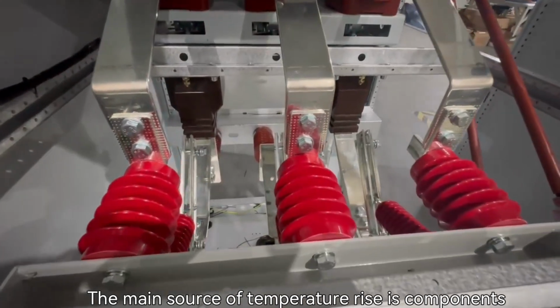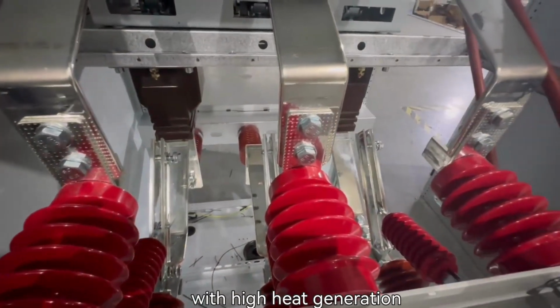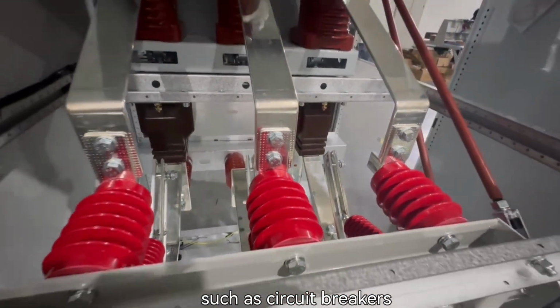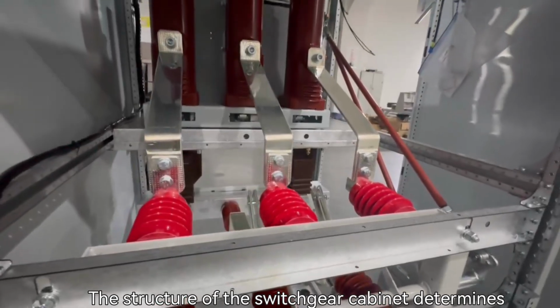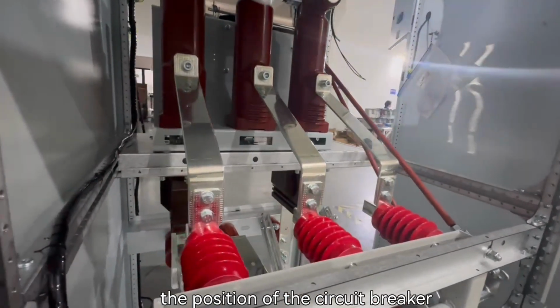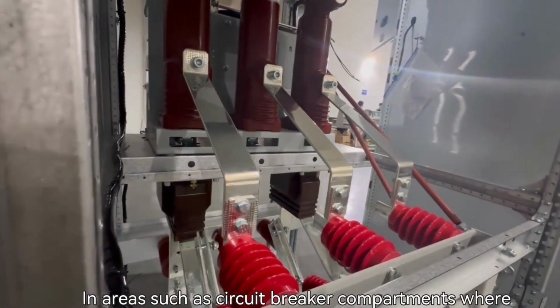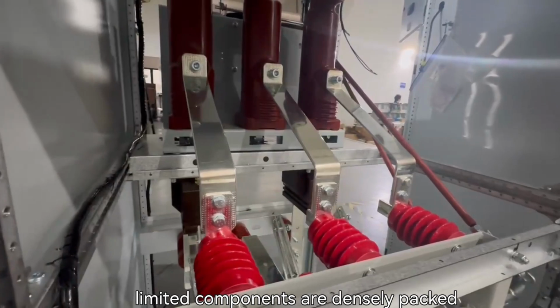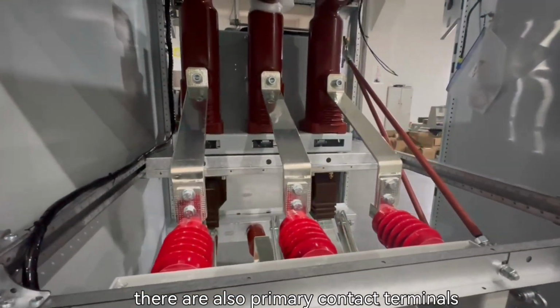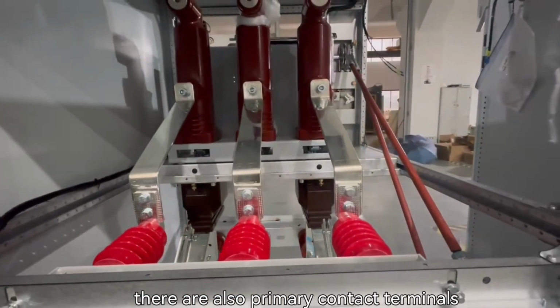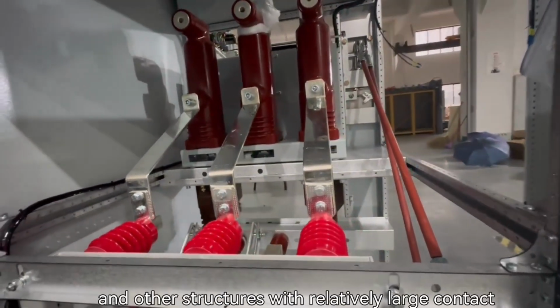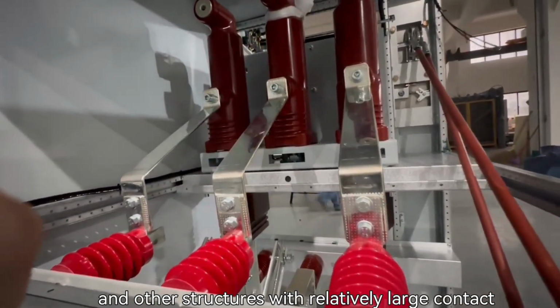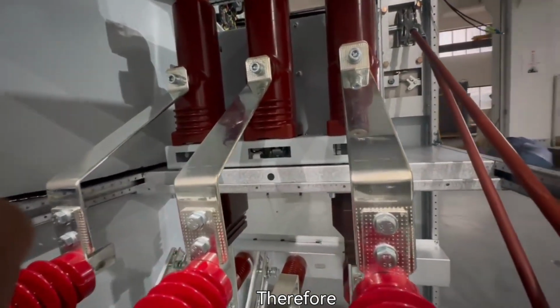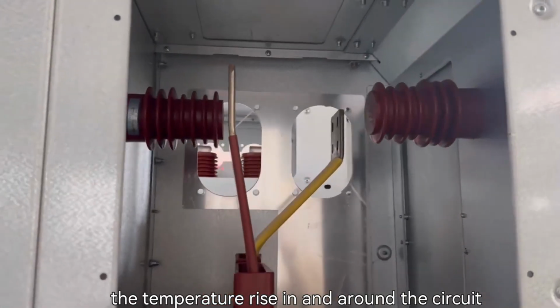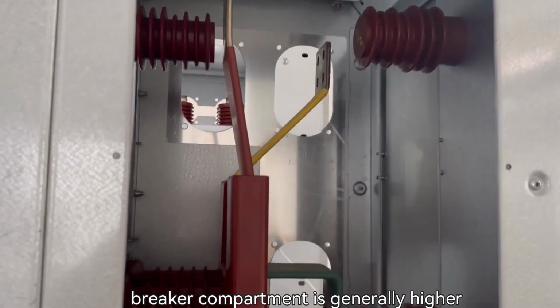The main source of temperature rise is components with high heat generation, such as circuit breakers. The structure of the switchgear cabinet determines the position of the circuit breaker. In areas such as circuit breaker compartments where limited components are densely packed, there are also primary contact terminals, connecting joints, and other structures with relatively large contact resistance. Therefore, the temperature rise in and around the circuit breaker compartment is generally higher.